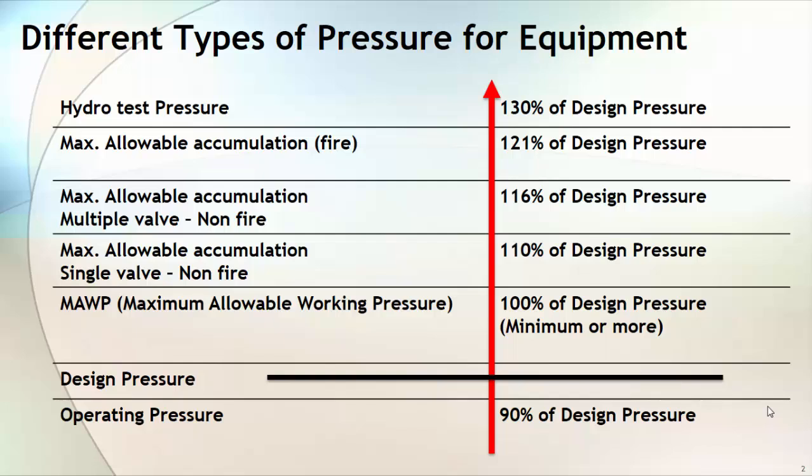Now it is very common that an 18 mm thickness plate can withstand more pressure than a 16.5 mm plate. So he will back-calculate, using this 18 mm thickness plate, what is the maximum pressure that this designed equipment can withstand. This pressure will become your maximum allowable working pressure. So now we have covered three terms: operating pressure, design pressure, and maximum allowable working pressure.